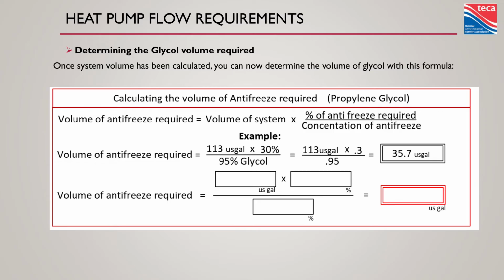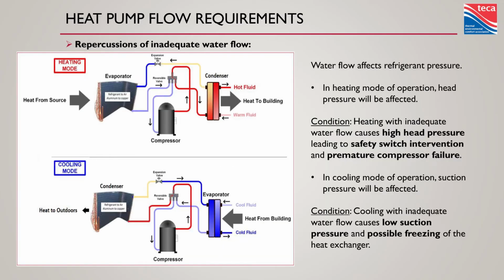So what happens if we don't have enough water flow? As I mentioned before, when we're in heating mode, pressures go up in the refrigeration circuit. We can't dissipate that heat. Things climb and climb. Things shut down to protect themselves. When it's cooling, our suction pressure starts dropping and dropping. Again, bad thing. We want to make sure we have ample flow through these systems.